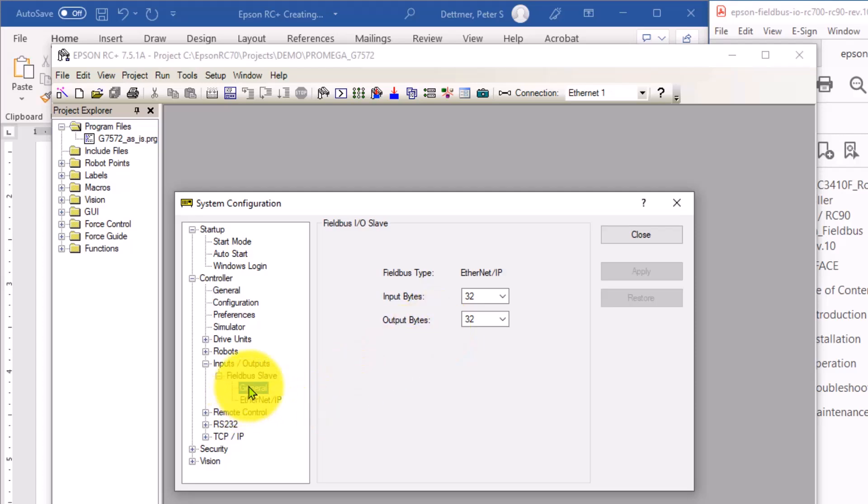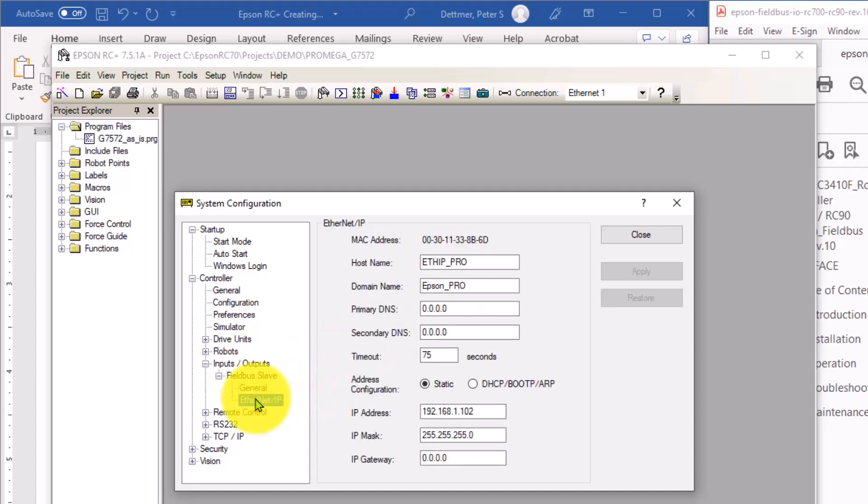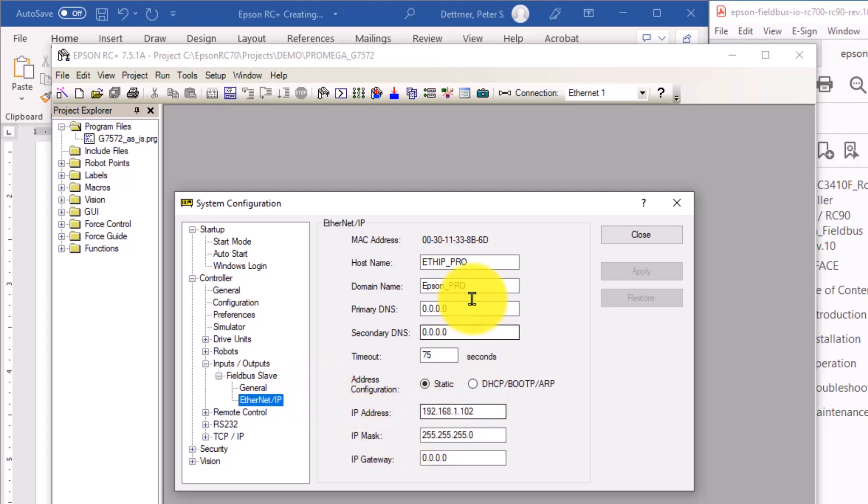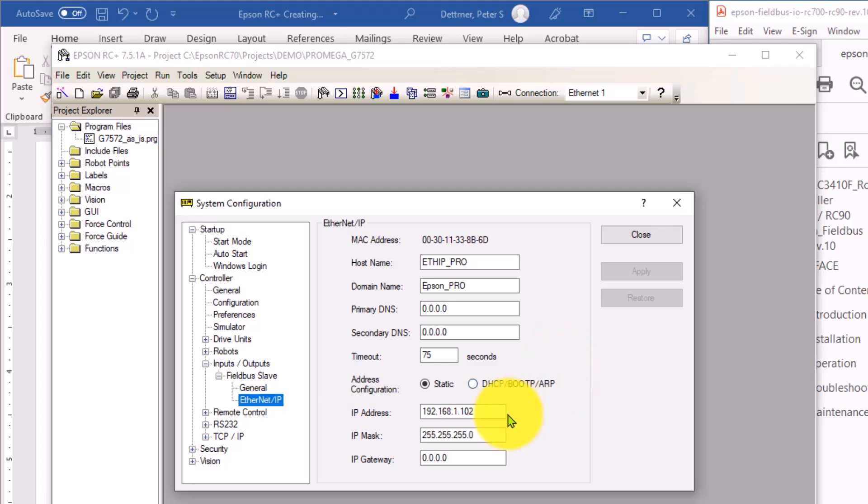Then within the general settings, again, this is the general settings of the field bus device. Ethernet IP, this is where you set up the IP address of the Ethernet IP card. You don't need these DNS settings, because we're just talking IP address to IP address. We want to make sure it's set to static so it doesn't change. But you need, again, an Ethernet IP address and the mask.